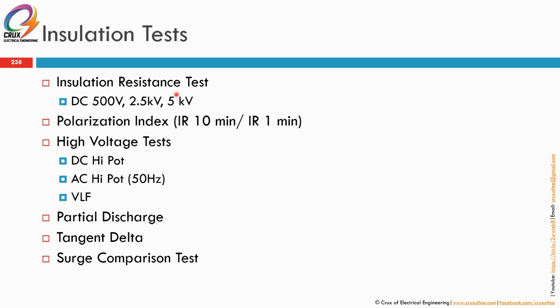So normally during your commissioning, you'll do the minimum IR test, PI if you have a machine, and for a transformer if you like to do it, and the third test will be the high voltage test, the AC high pot or DC high pot. But for low voltage, normally we don't do a high voltage test. For anything MV, we'll do it at site. So these are the 3 tests that are normally the minimum required for commissioning of the equipment. All these tests are to test the insulation of the equipment, whether the insulation is good or not.